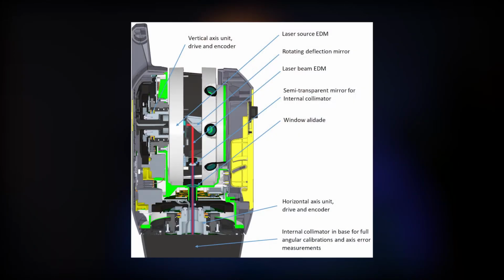This collimator tube and sensor is what Trimble has been able to miniaturize and include in the base of every X7 laser scanner. When the calibration procedure is started before each scan, the instrument sends laser pulses down into the base where they enter an internal collimator, and the instrument alignment is checked and adjusted. You're carrying a calibration laboratory with you to every scene you and your instrument go to, and the instrument is checking itself with that equipment before each and every scan, ensuring your data is of the highest integrity.